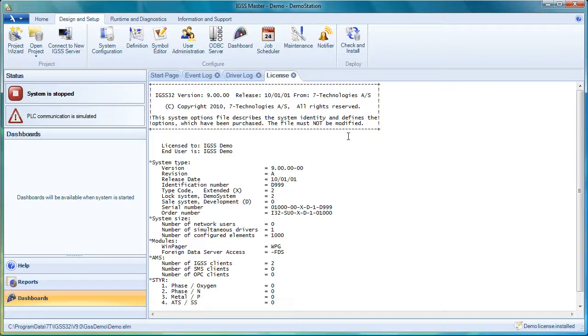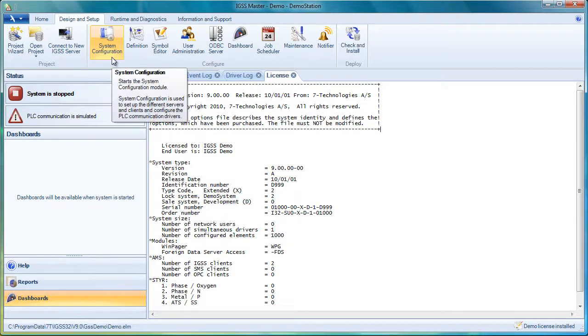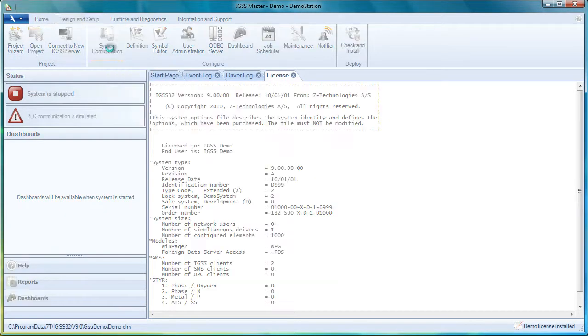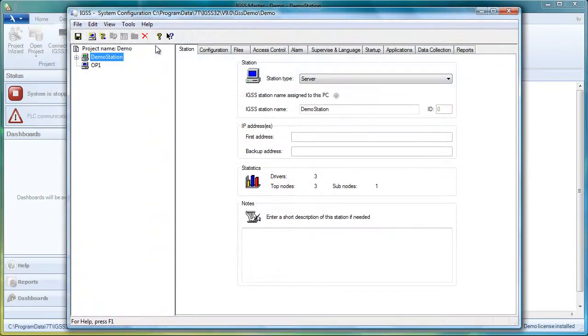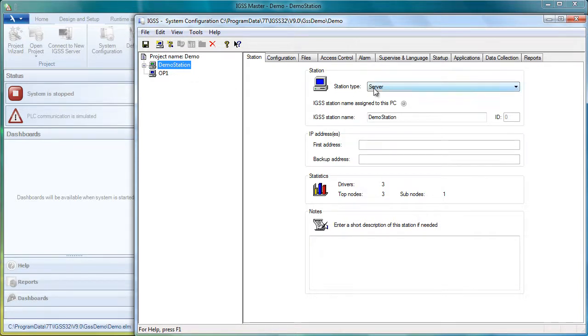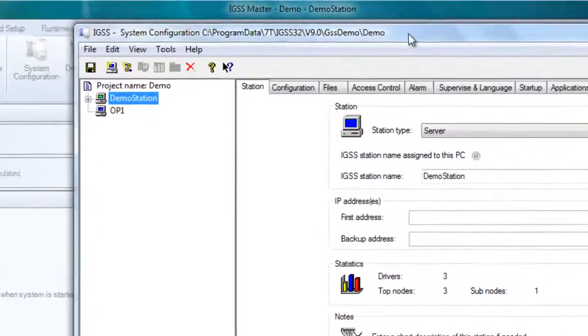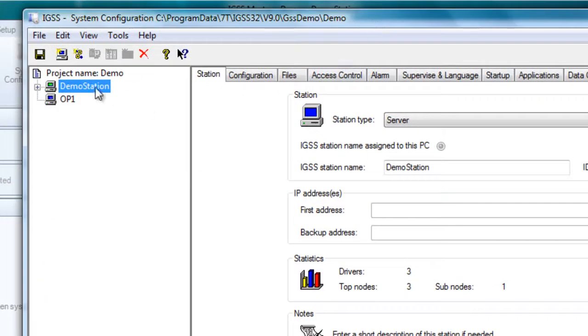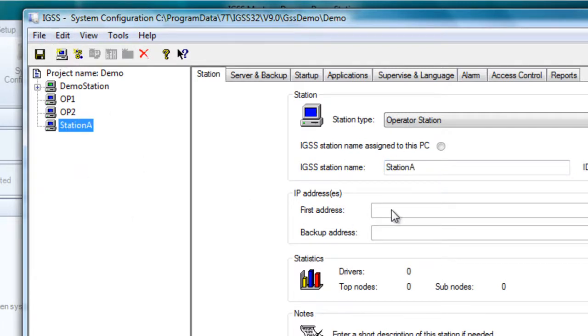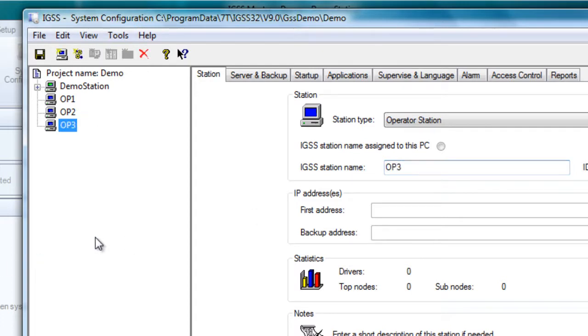And finally, let's talk a little bit about multi-user systems. In a multi-user system, you will actually create a new project from the project wizard. Then you'll go into your system configuration module and you will set up the number of stations that you need. Here we have a demo station that is the server in our system and we have one operator station, but we can put on more operator stations. It's very simple. Just click on the icon new station, you get a station A, change it to OP2, let's put on a couple more, OP3, etc. Now you've set up a multi-user system and what you want to do now is you want to distribute it to the operator stations.